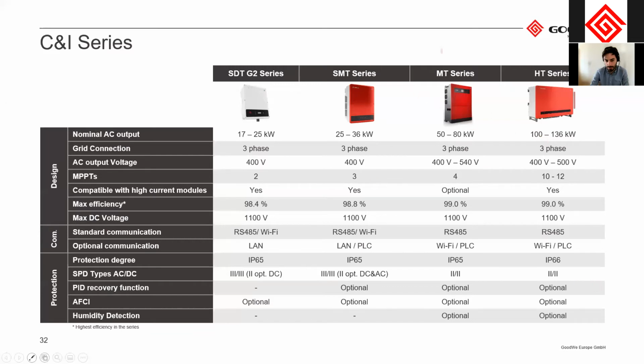Also, what you can see here, the higher you go in the range, you get additional protection, optional protection features that you can add. So for example, you have the PID recovery function, potential induced degradation, which happens to the modules over time. And then we have a function to reduce this to prolong the lifetime of the PV modules. The AFCI is an arc fault circuit interrupter, which can interrupt arcs happening on the DC side, and also a humidity detection for the MT and the HT series.